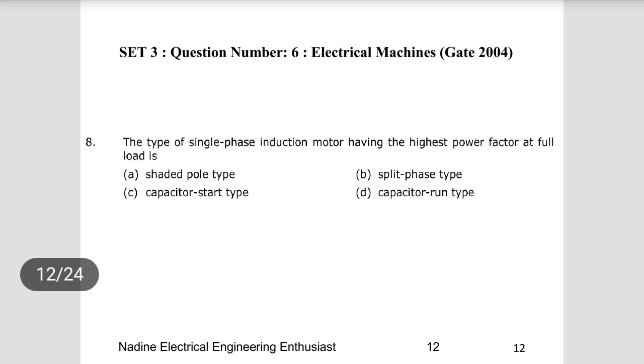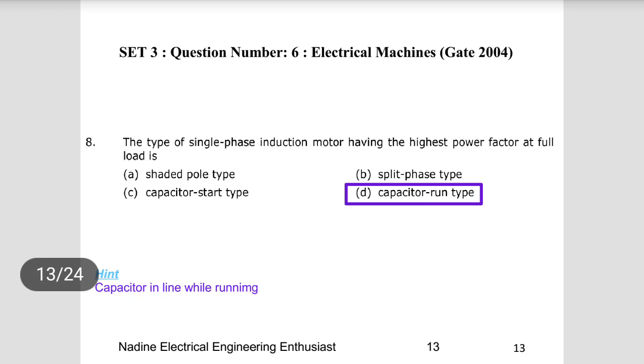Sixth question: which type of single-phase induction motor has the highest power factor at full load? In a capacitor-start motor, the capacitor is present only during starting. In a capacitor-run motor, the capacitor is always connected with the winding during running. Because the capacitor is always connected, the power factor of operation is higher. So the capacitor-run type motor has the highest power factor. That is the correct answer.